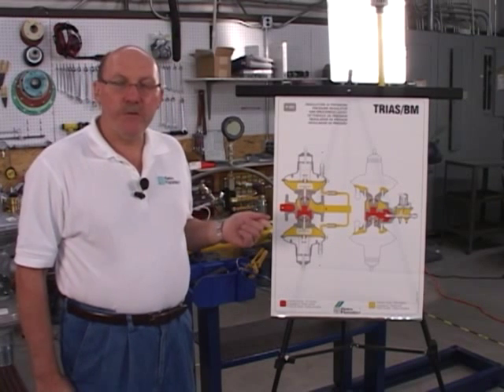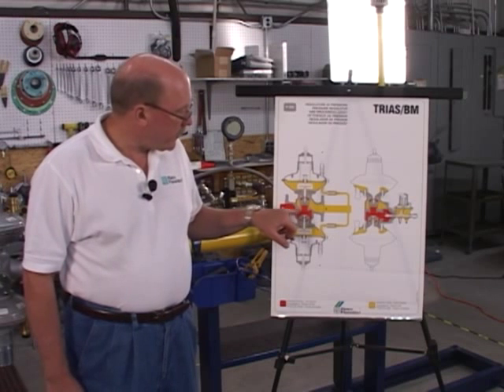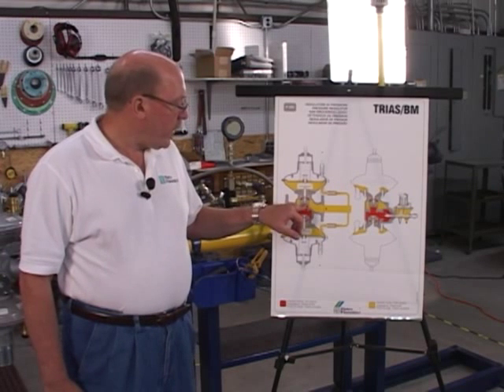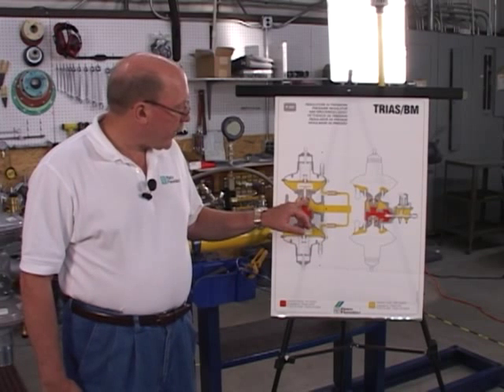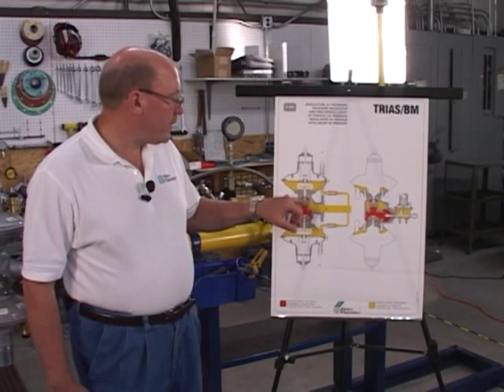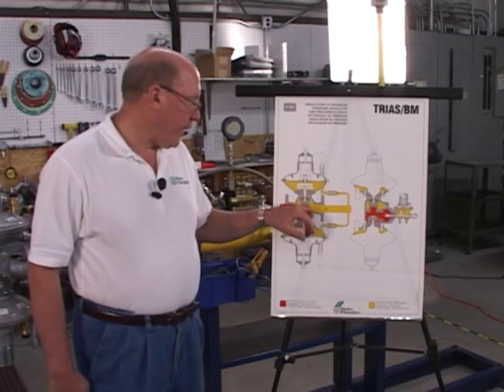The TRIAS incorporates what we call a balanced valve design. The inlet pressure comes into the regulator, and on the bottom of the regulator cartridge we have a small hole and a hollow stem. The gas comes up through the regulator through the stem into what we call a balancing piston.